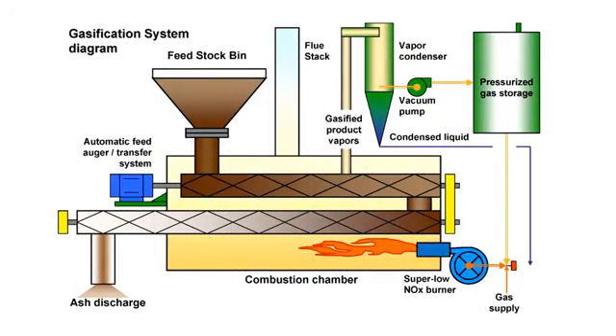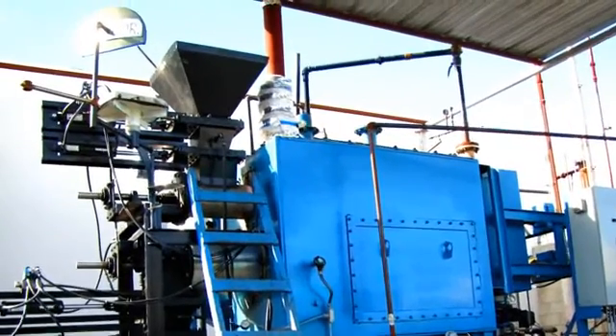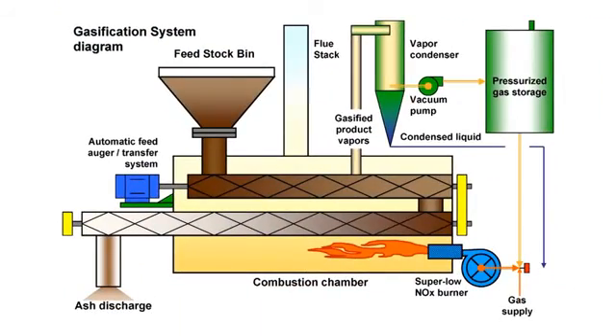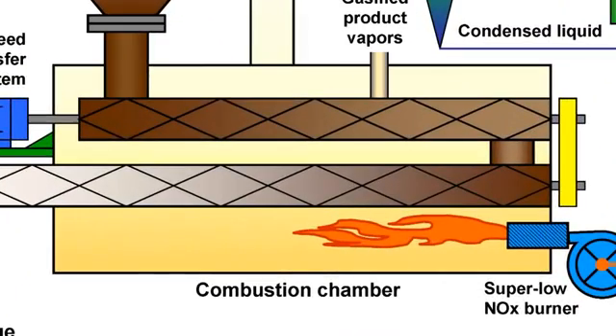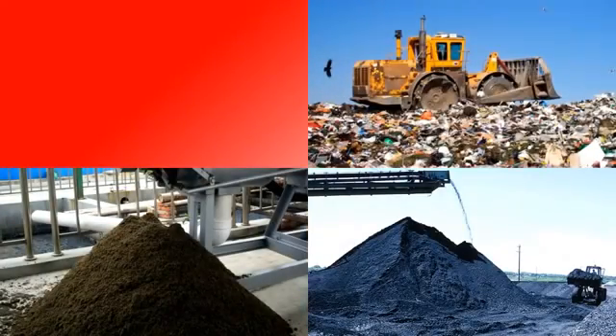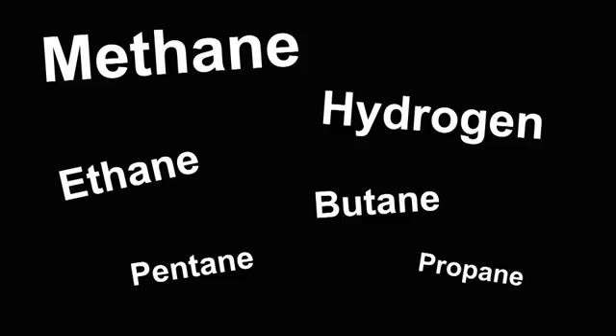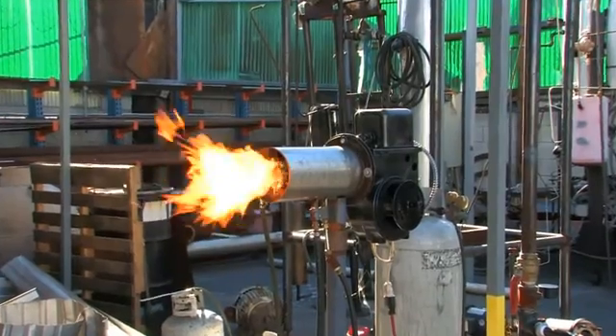Let's take a closer look at step 2, since that's where all the magic happens. The feedstock is continuously fed into ACTI's highly efficient pyrolysis system. It is important to note that the processed materials are indirectly heated in a closed oven-like chamber, known as a retort, where temperatures reach 900 to 1200 degrees Fahrenheit, depending on the type of feedstock being processed. This heated environment is oxygen deprived, ensuring the feedstock never burns, but rather is distilled into its basic chemical components, which are all flammable and energy-rich.